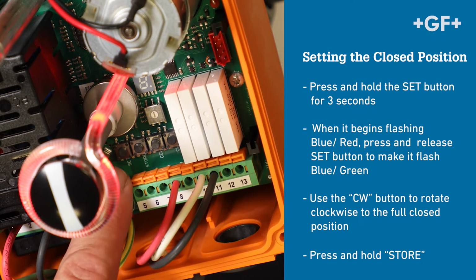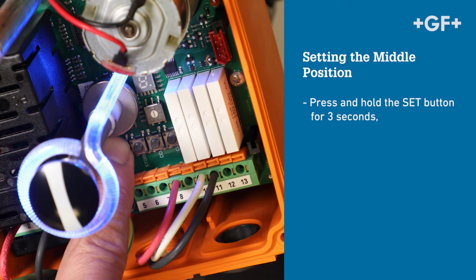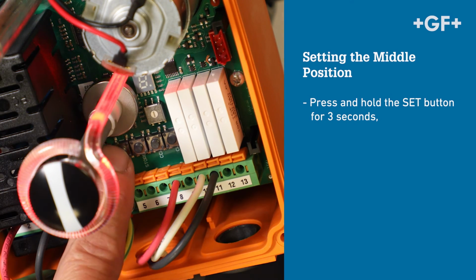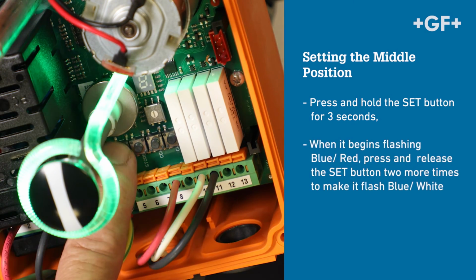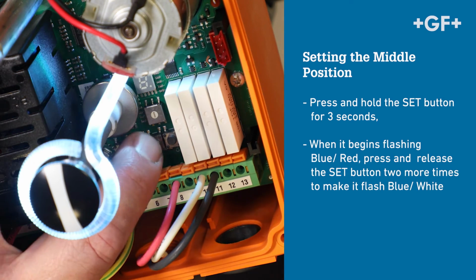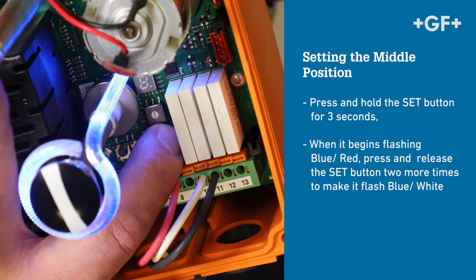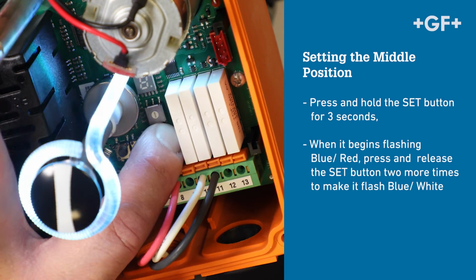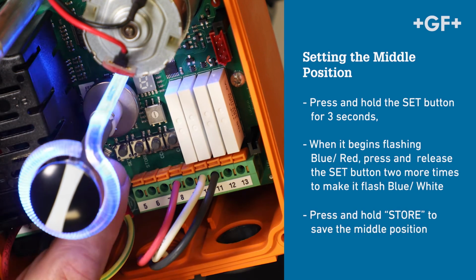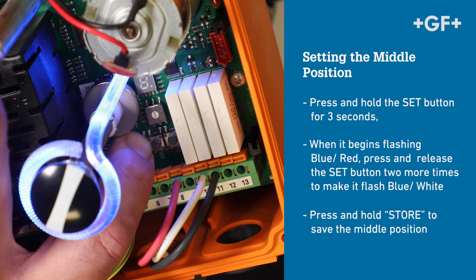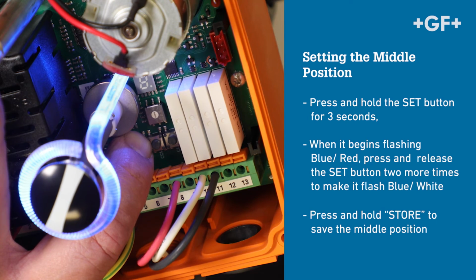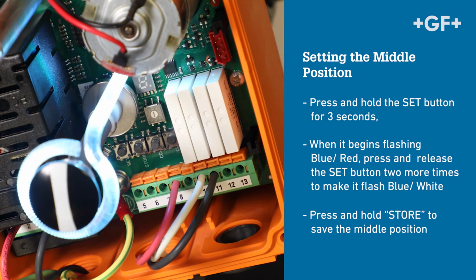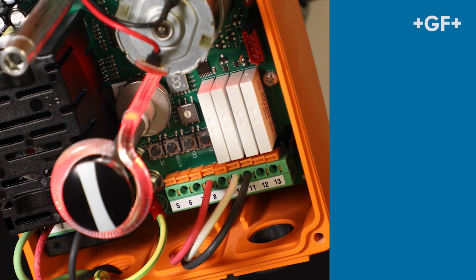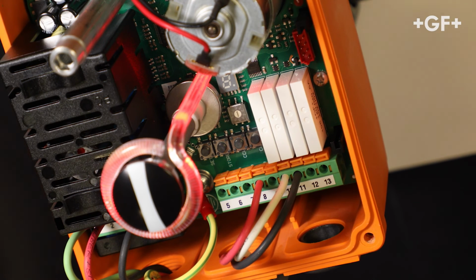Setting the optional middle position. Here you'll need the light tube flashing blue and white. Depending on the direction that gets you to the middle position quickest, use either the CW or CCW button and rotate the actuator to that position. Then, press and hold Store. Congratulations! You've programmed the end stops on your EA Series electric actuator.